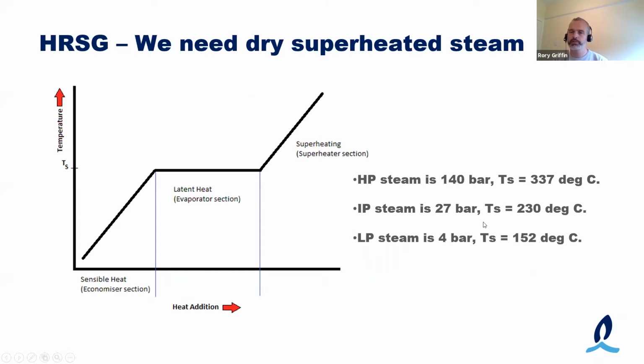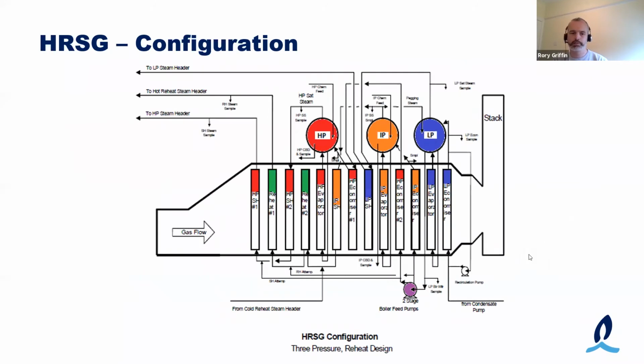So what that means is you can take advantage of the temperature profile from 650 down to 85, and you can end up with 3 systems giving you superheated steam, which then can feed into a triple cylinder steam turbine like what we have. If you're to get the same steam flow, you'd end up with bigger pipes, more capital expense. So by having this size boiler with triple pressure, you get more steam flow to your steam turbine. So I'll just go to the next slide here, and I'm going to try the magnifying glass here, see if this can help.